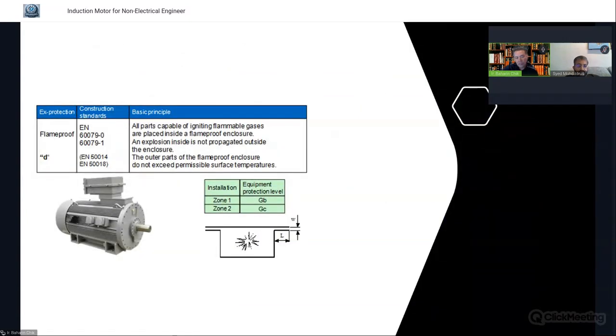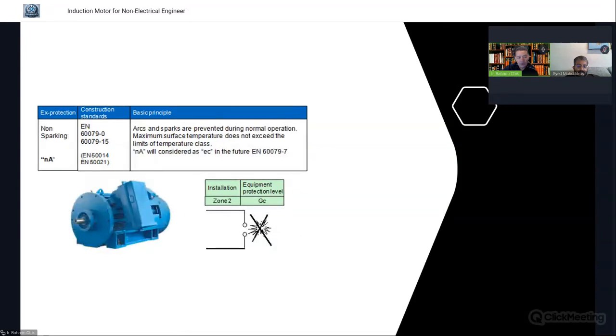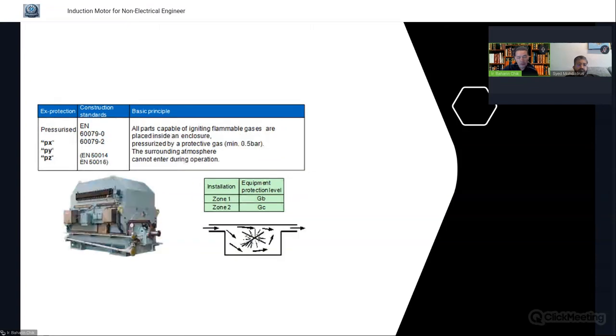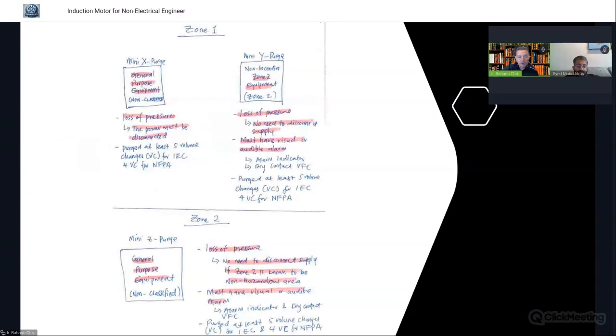And then the motor also needs to be designed for its installation. For example, in zone 1 and zone 2, we can use EXD motors. In zone 2, we can use EXNA motors. Or if not, then we can use EXP motors in zone 1 and zone 2. So the choice depends on the economic factors and where the motors are going to be installed. So this explains the difference between the motors with PX, PY, and PZ.